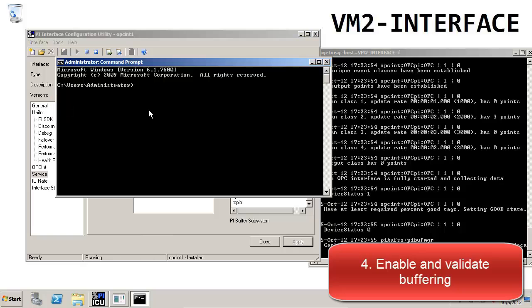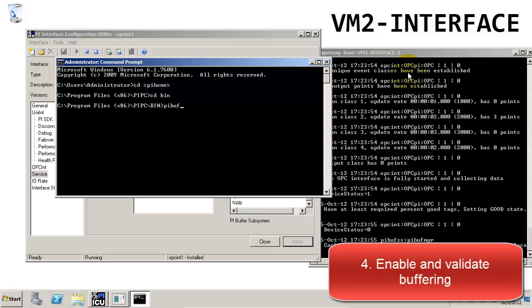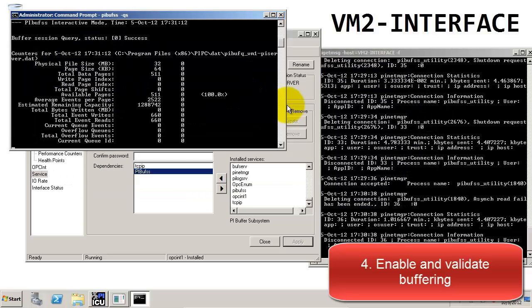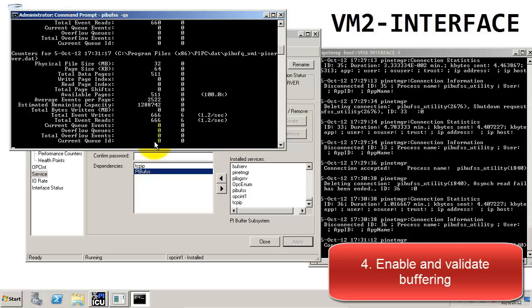A way that we can check that the data is passing through the buffer correctly is by using a utility called PI Buff SS. This is located in the PI Home slash bin directory. Once we get to the bin directory, we can type in PI Buff SS dash question mark, which will give us a list of the parameters we can use with this utility. We're interested in seeing what's in the queue, so we'll use dash QS, which will bring up the queue statistics of the buffer. You'll notice that there are two columns of numbers: the left-hand column shows the totals, whereas the right-hand column shows the number of changes since the last refresh. The queue statistics refreshes every five seconds.